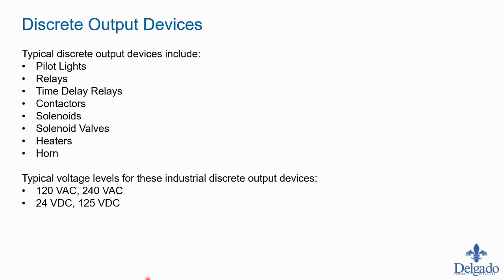We're still talking about discrete devices — things that will be on or off with no in-between states. Our typical discrete output devices include pilot lights, relays, time delay relays, contactors, solenoids, solenoid valves, heaters, and horns. The control voltages for these devices are typically either 120 volt AC or 24 volt DC, and we'll look at each one in more detail.